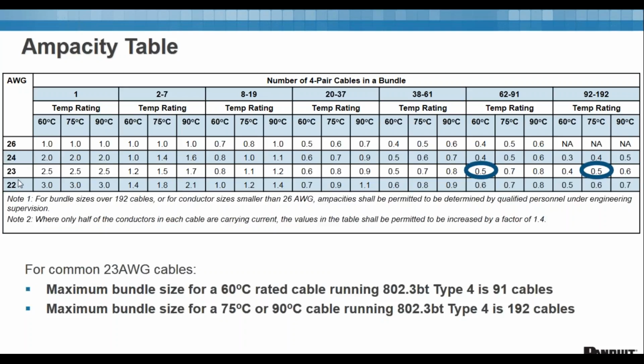For some commonly rated cables, like a 23 gauge, which is a lot of Cat 6 cables, at 60 degrees C cable rating, you could have a bundle of up to 91 cables. A 23 gauge cable with a 75 degree rating could have up to 192 cables. So again, this isn't very restrictive. A 23 gauge, 75 degree cable is a pretty common cable, and 192 bundles isn't very restrictive. However, you're going to have to validate that if you have some large bundles, you're falling within that 192 range.